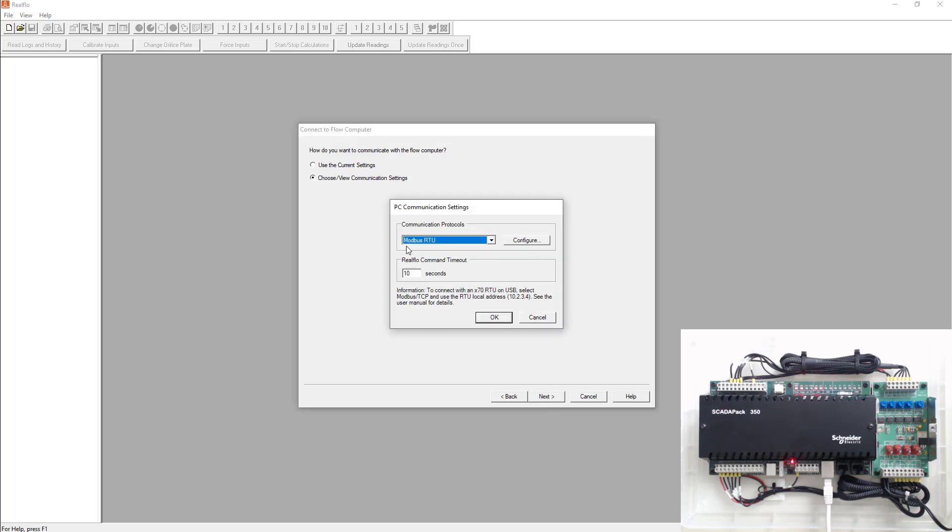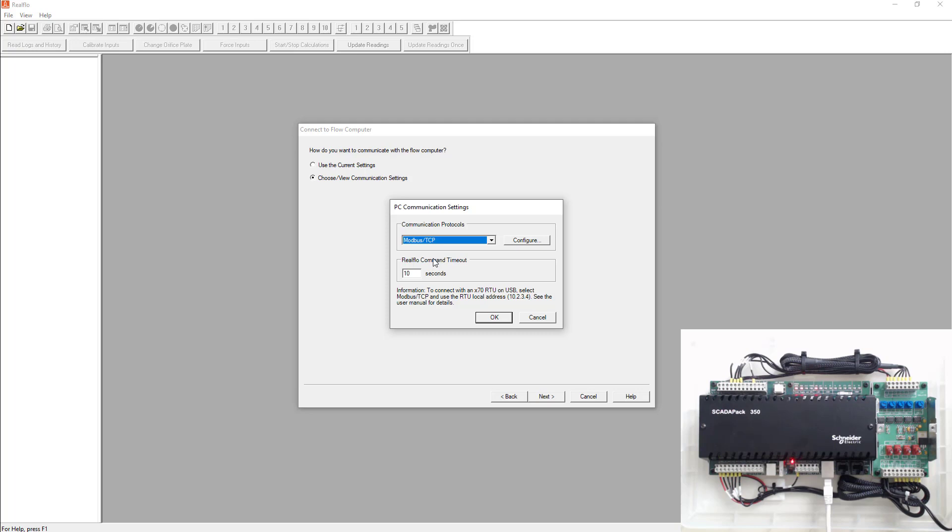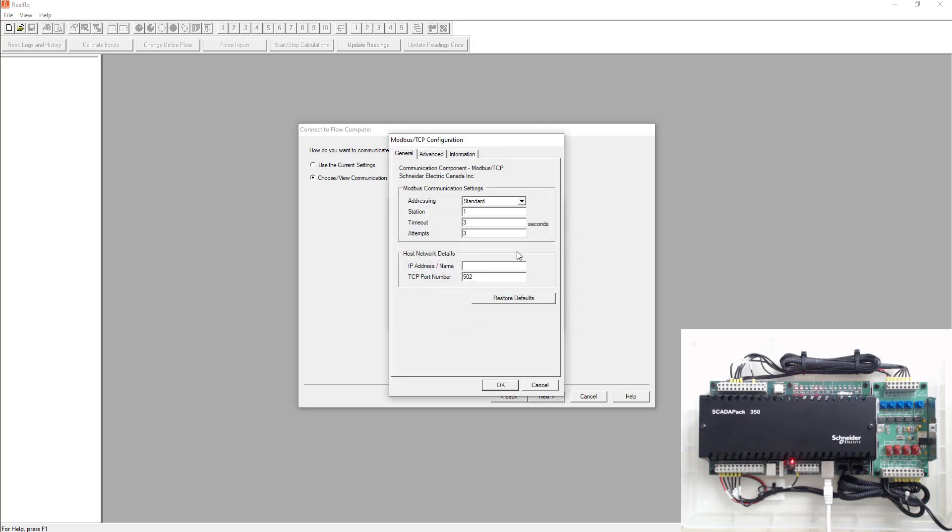In here I don't want to use Modbus RTU. I want to use Modbus TCP because that's how I'm connected to it. Try not to use Modbus RTU or over serial. It just takes a lot more time. For these labs it's probably a lot easier using Ethernet so that's what I'm going to use. In here I know my IP address is 192.168.0.159.